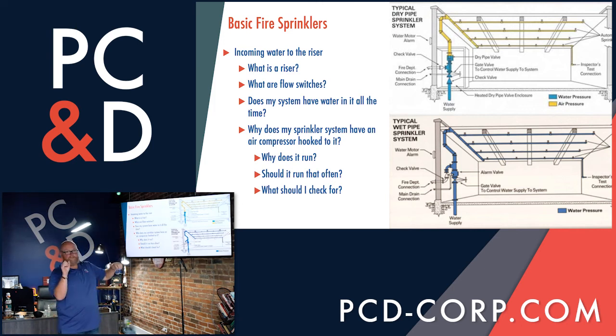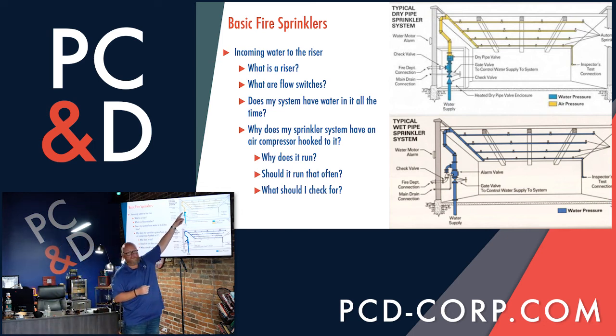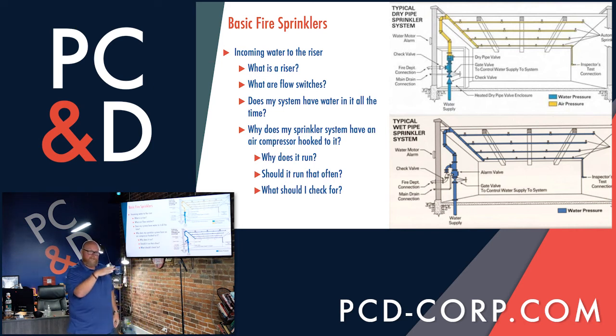Once that air is released and the air is gone, we now have lost the pressure that's on top of that valve holding back the water. When that air releases quickly, your air compressor is going to come on and try to run, but it'll never keep up, because now it's too late. As soon as that air is all gone quickly, the water pressure will overcome the valve. The valve then opens. When that valve opens, there is a latch inside of that valve that will hold that valve open.